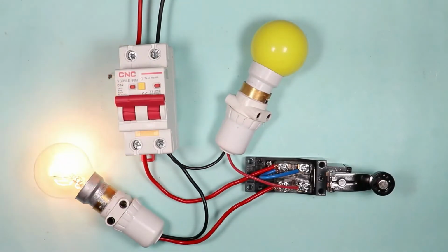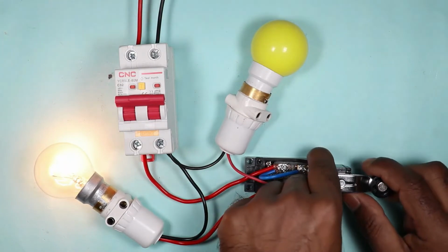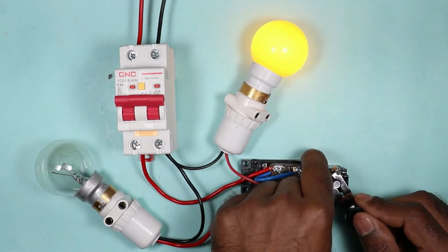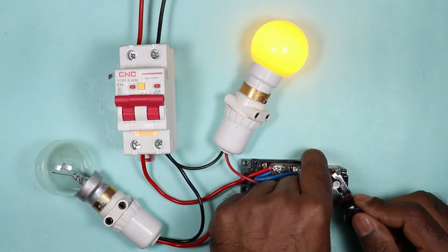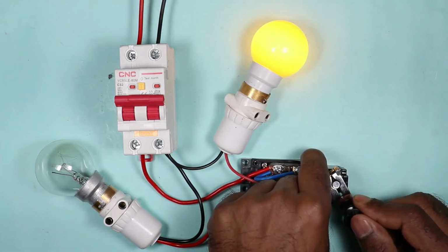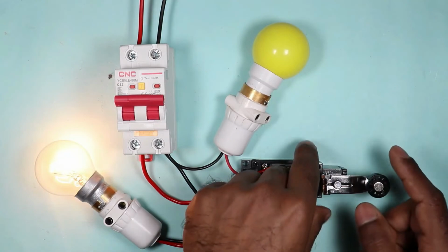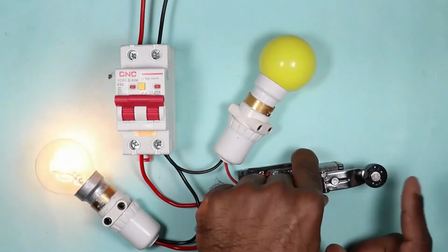On turning on the MCB, you can see this lamp is on now. This lamp was connected with NC contact, so it is turned on. Now if I operate this limit switch, then you can see the lamp connected with NC is turned off and the one with NO turned on. This means now the limit switch is generating an output signal to NO contact and stopped the signal to NC contact. On again releasing, this comes back to normal position. On again operating, you can easily understand what's going on.